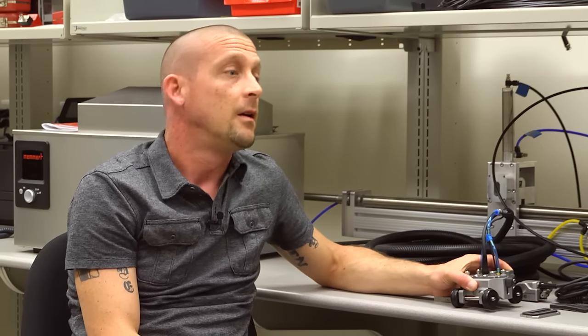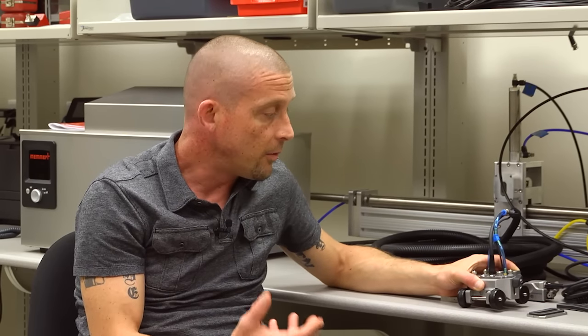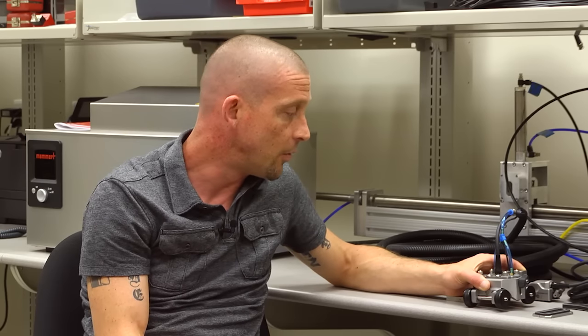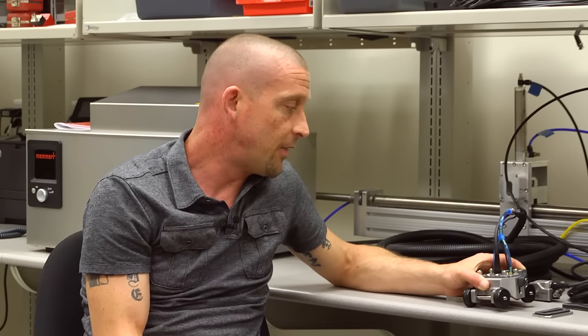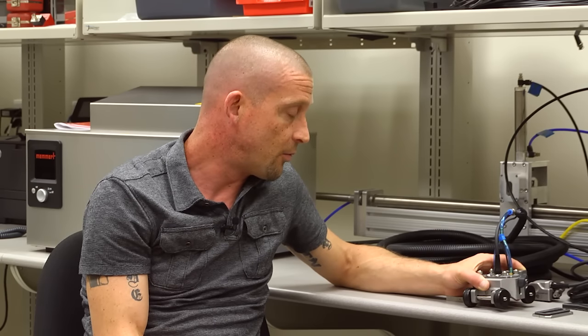The other benefit is the flexibility of phased array. We have the ability to steer beams at different angles, and the flexibility to change the focus spot. So if there's a certain area where we think corrosion might exist, or for a secondary scan, we can refocus the beam, sometimes in the depth axis, to get a better profile. We also have the flexibility of being able to program it directly on the instrument.